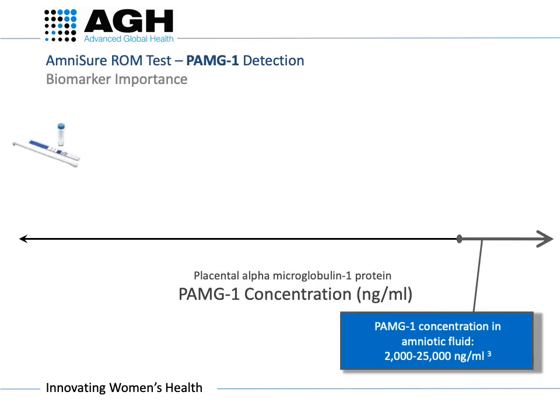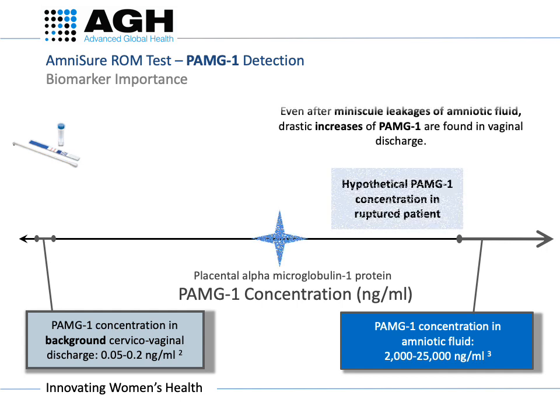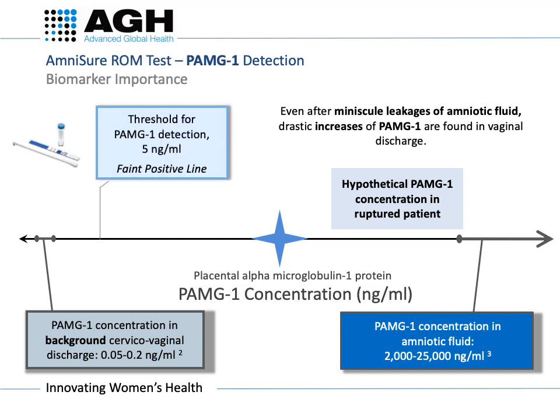The test strip has highly sensitive antibodies to detect the presence of the PAMG-1 protein in vaginal discharge. Normally, there are extremely low concentrations of PAMG-1 in vaginal discharge and a much higher concentration in amniotic fluid. Clinically significant leakage of fluid from the cervical os due to a rupture will result in a significant increase in the PAMG-1 concentration in cervicovaginal discharge. The AmniSure test has a very sensitive threshold for detection at 5 nanograms per ml.